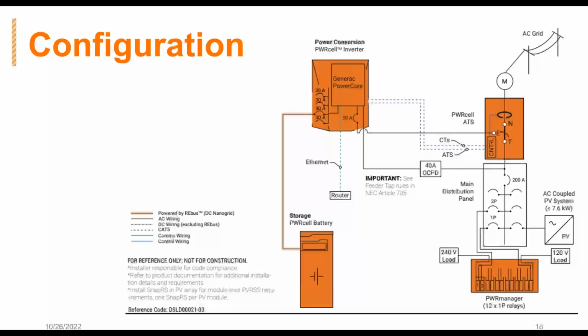How many amps was the power manager? Okay, I want to maybe clarify here. The power manager has 12 single pole relays. If you have a 2-pole load, like a dryer, for example, you're going to take up 2 of those relays. Each one of those relays is rated for 60 amps.